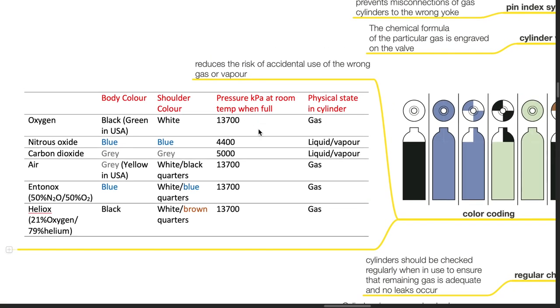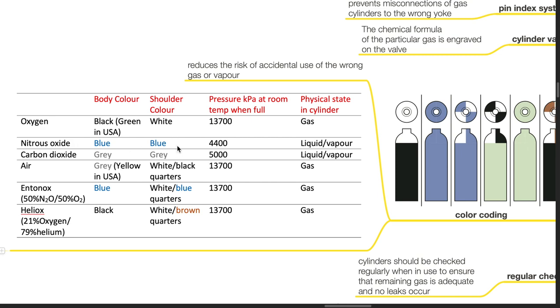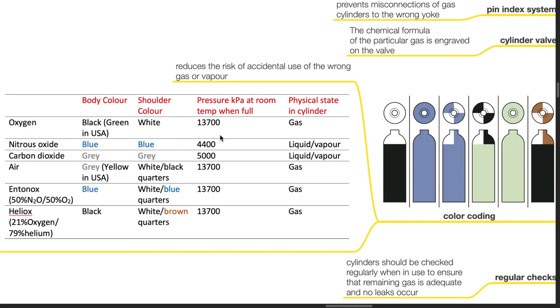For oxygen, the body colour is black, shoulder colour is white, pressure at room temperature when full is 13,700 kPa, and physical state in the cylinder is gas. Nitrous oxide cylinder has a blue body colour and blue shoulder colour. Pressure is 4,400 kPa at room temperature when full. Physical state in the cylinder is liquid and vapour.